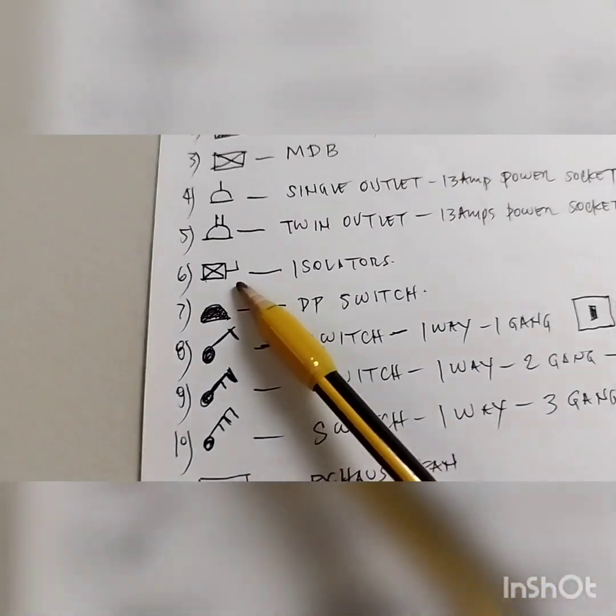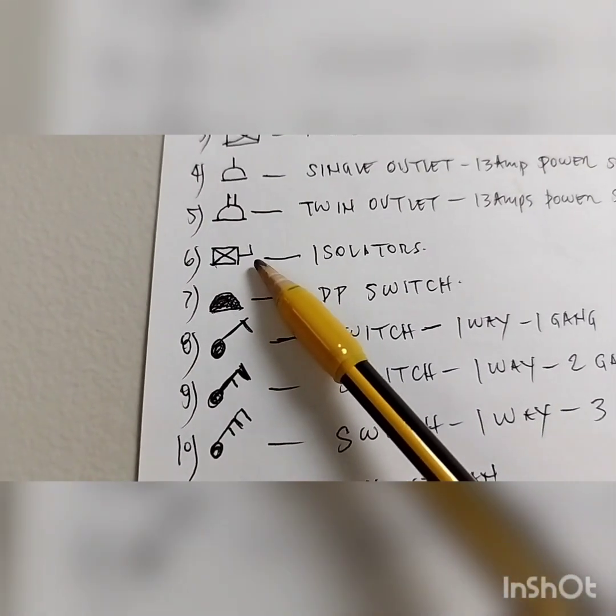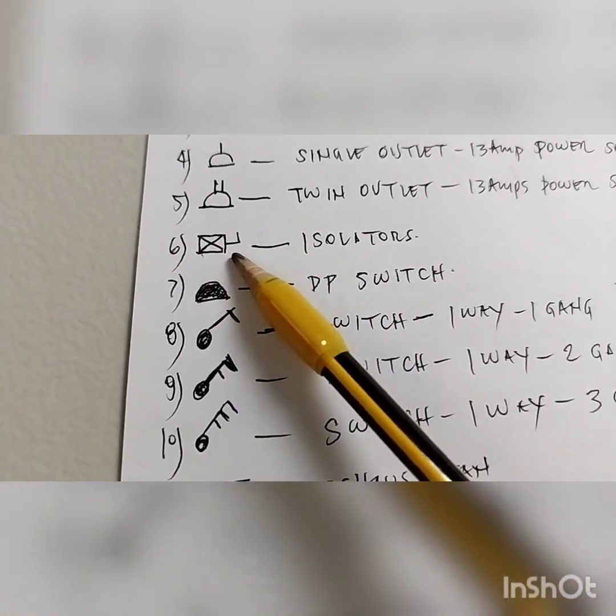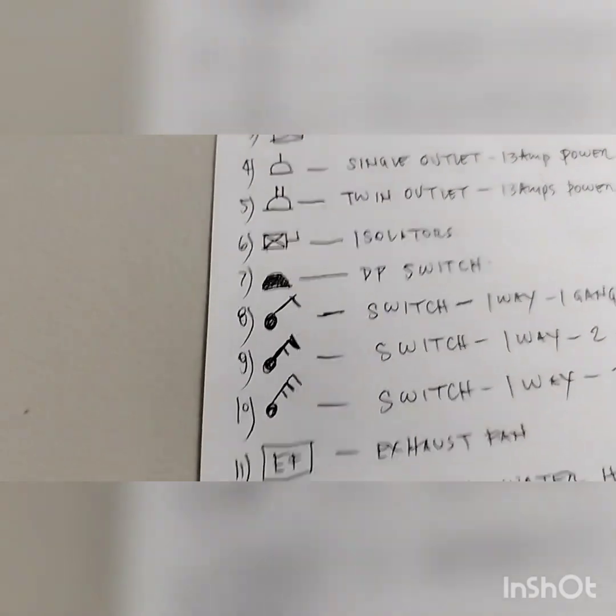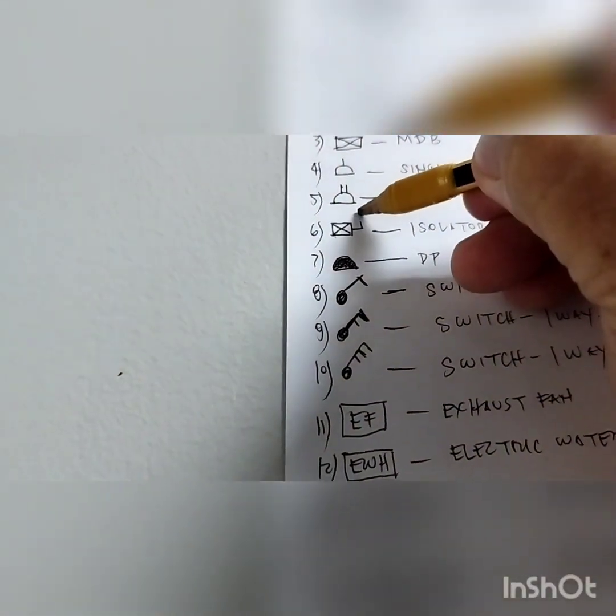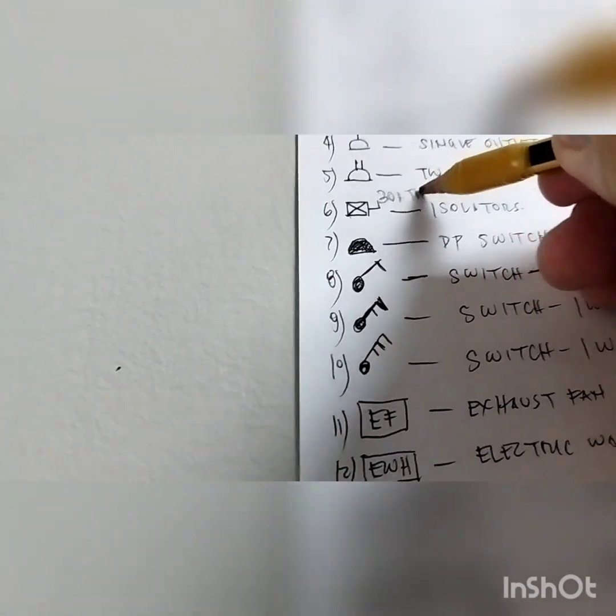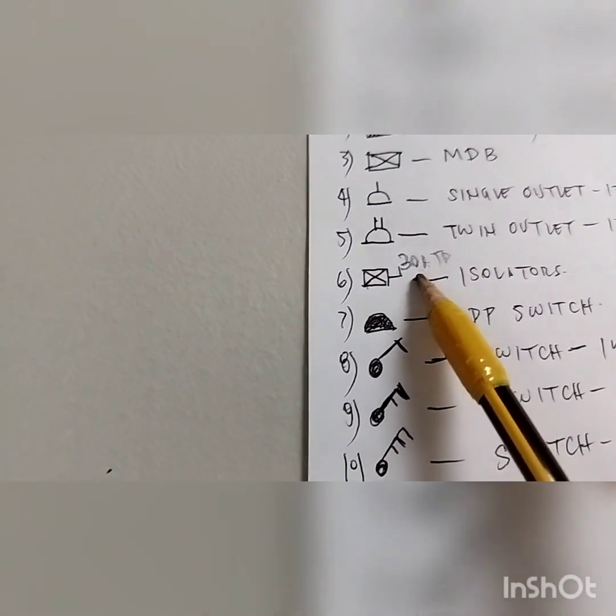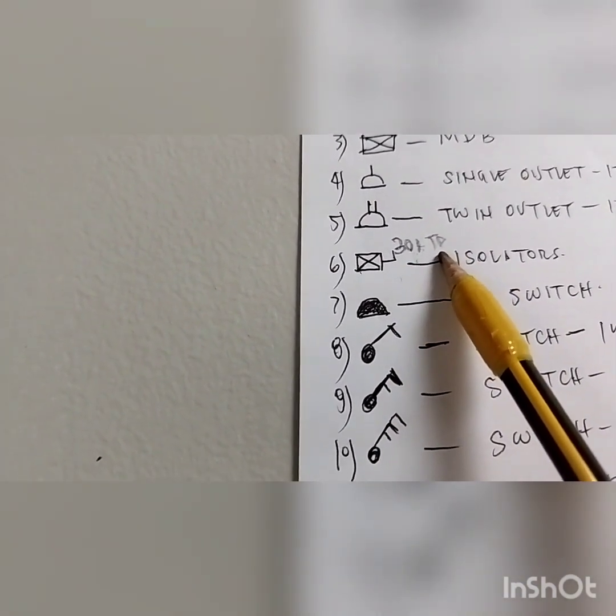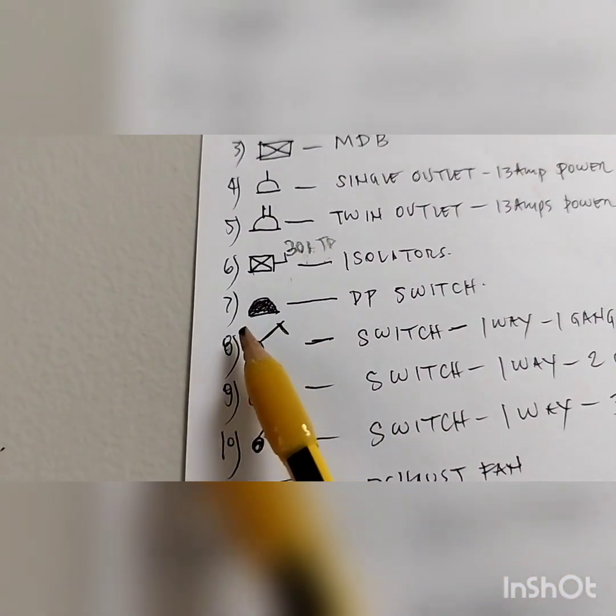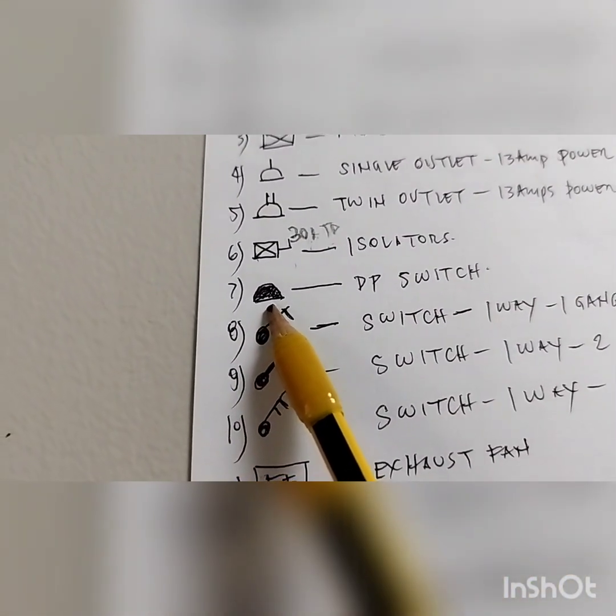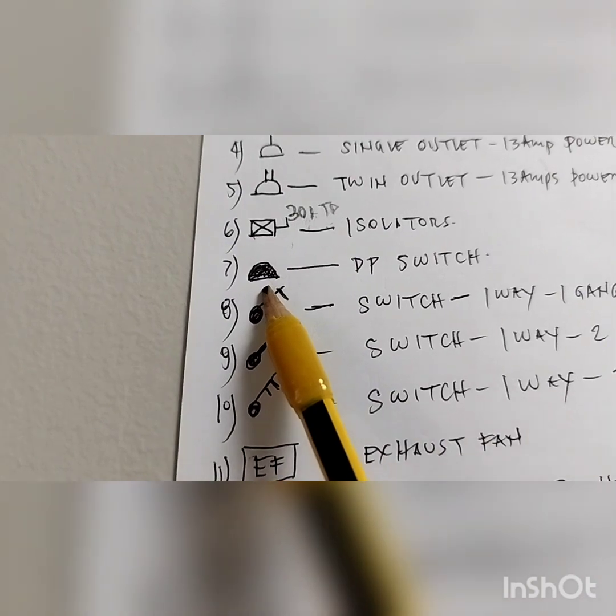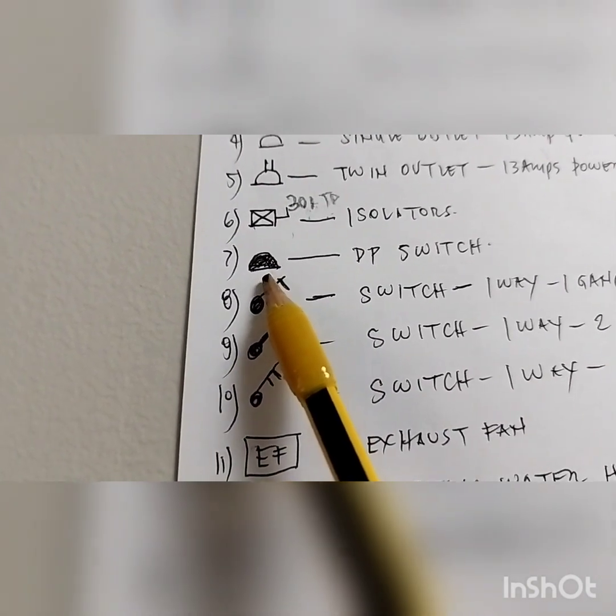This symbol is for isolators — isolators for FCU, any motors. They put the ampere and phase rating on there; for example, you might see '30 amps TP,' which means it is an isolator rated 30 amps, triple pole, three phase. This symbol is for a DP switch — for example, a DP switch for AC, a DP switch for an electric water heater, or a DP switch for a hand dryer.